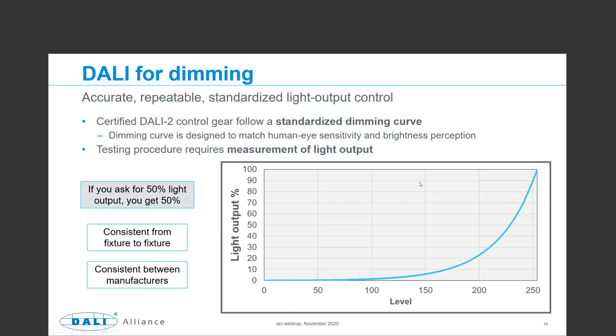Now this results in a statement that we can make: ask for 50% light output, you get 50%. Because of the testing, we ensure the control gear with a suitable connected lamp follows this standardized dimming curve. It's consistency. And this is consistent from fixture to fixture, so that's within the same manufacturer, but also between manufacturers. So everyone follows the same dimming curve, which is tested. So you've got that consistency.